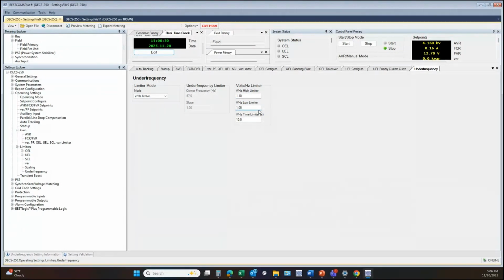So again, you don't want that at 1.00, because if you're at 1 per unit frequency with a setting of 1.00 for this limiter, it won't allow your generator voltage to go any higher than your rated voltage. Normally you want at least some room to make adjustment, 5 or 10% above your rated voltage. So you set this volts per hertz limiter accordingly. And if your frequency starts to reduce, then it reduces your generator voltage, just like the under frequency limiter did.